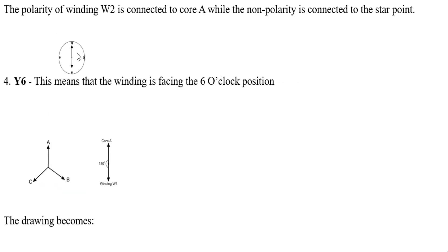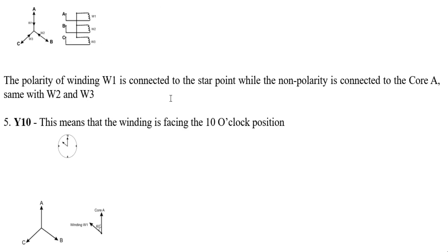Y6 shows 6 o'clock. At 6 o'clock the windings are 180 degrees apart, and the winding arrow is facing down. This means the polarity sides of all three windings are connected to neutral, while the non-polarity side of W1 is connected to A, the non-polarity side of W2 is connected to B, and the non-polarity side of W3 is connected to C.